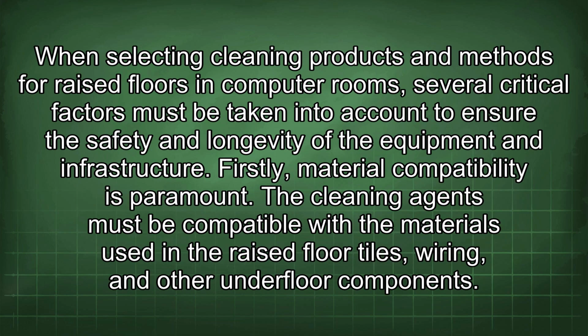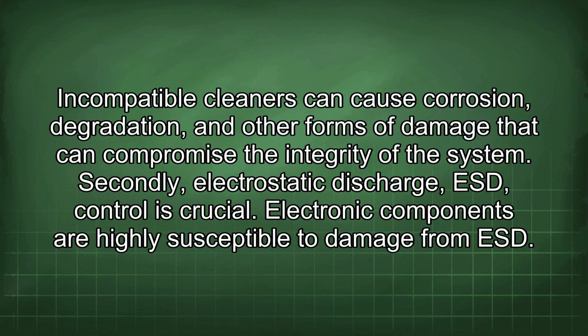failure. When selecting cleaning products and methods for raised floors in computer rooms, several critical factors must be taken into account to ensure the safety and longevity of the equipment and infrastructure. Firstly, material compatibility is paramount. The cleaning agents must be compatible with the materials used in the raised floor tiles, wiring, and other underfloor components. Incompatible cleaners can cause corrosion, degradation, and other forms of damage that can compromise the integrity of the system.